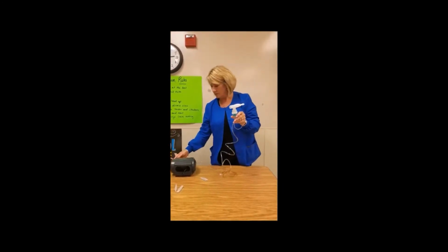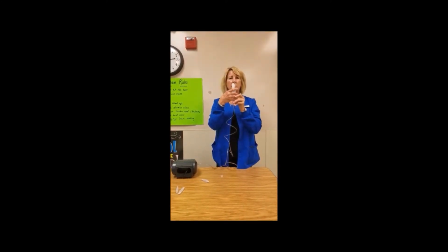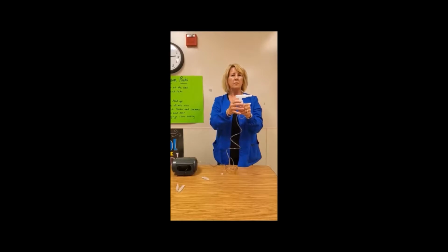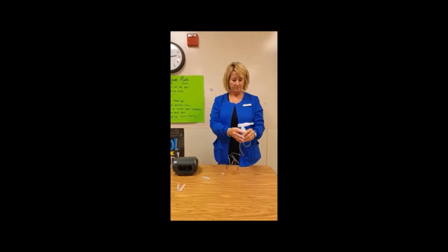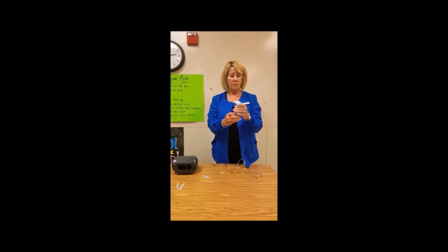Turn on power switch. Make sure the mist is visible and start treatment. Place mouthpiece in mouth or mask over face. When mist is no longer visible, turn off power switch. Have student rinse mouth with water and spit. Remove nebulizer cup from tubing, rinse cup with water, and allow to air dry.